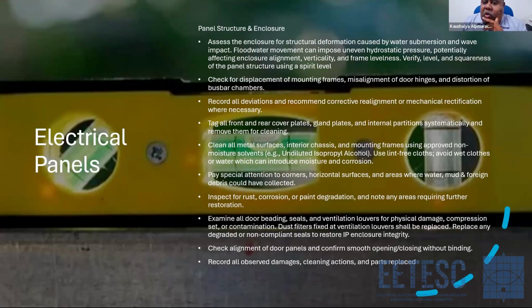Pay special attention to corners, horizontal surfaces, and areas where water, mud, foreign debris can have collected. Inspect for rust, corrosion, or paint degradation, and note any areas that require further restoration and further treatment as well. Examine all door beadings, seals, and all to ensure your IP rating. If you can, increase your IP rating as well during this rehabilitation work. Check alignments, record everything you did.